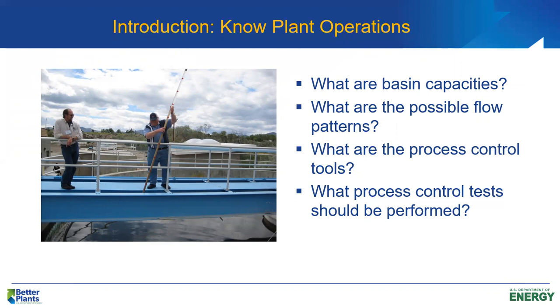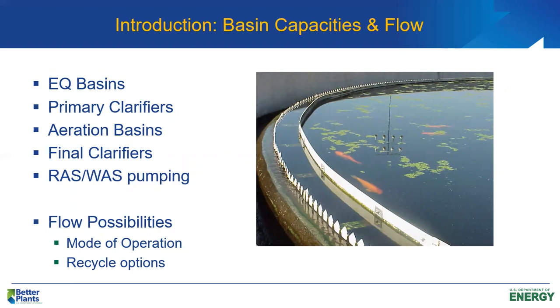There are a number of tests we can use to give us data about how the activated sludge process is performing. Those tests are absolutely critical because they give us the information to help us make decisions about process control. We need to know basin capacities and flow rates. If we have EQ basins — most municipal wastewater treatment plants in the United States do not — that's a disadvantage in that when we have high hydraulic loadings, we don't have a way to smooth them out. But if we do have EQ basins, that gives us capability to handle high hydraulic loadings.